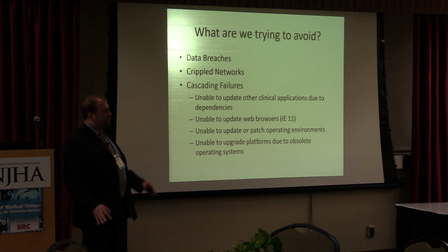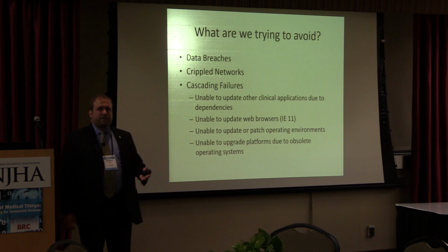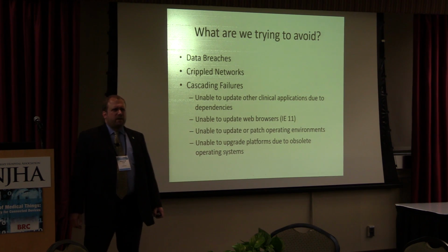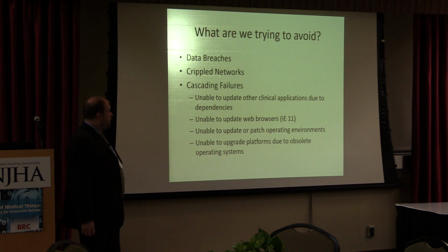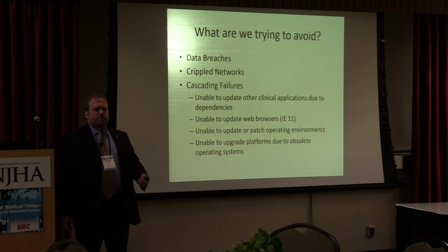And what I mean by cascading failures has multiple aspects. Number one, you have a clinical application or device in a certain application version or software version. You can't update other clinical applications because of it. So because you have this one device out there, you can't update everything, cascading down the road, leading to a cascading failure. You have clinical applications that haven't been updated to work with newer web browsers.